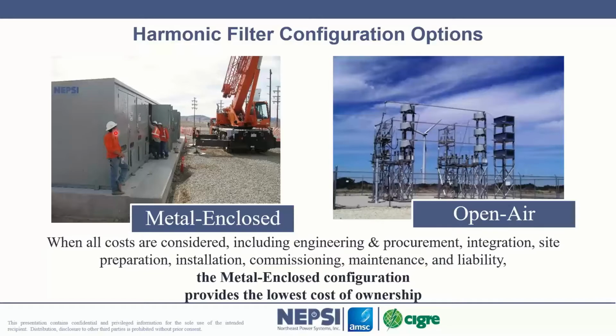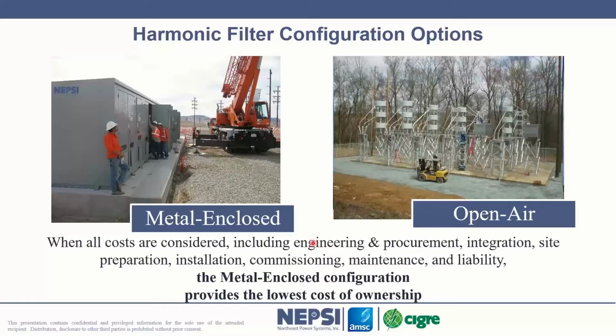The open air solution, the one to the right here, is also a filter, and it consists of air core reactors rather than iron core. So a big difference between metal enclosed and open air. The primary difference is this air core reactor. Instead of the inductor, which tunes this capacitor branch sitting behind it, being an iron core reactor, it's an air core reactor. So we're going to talk a little bit about air core and iron core reactors. And incidentally, this box here to the right, what is it? It's a resistor. So we put the resistors on top of our enclosure when we have resistors associated with our harmonic filter. In this case, you can see that the resistors are put off to the side. So open air and metal enclosed, they're the two configurations we're talking about. And we'll be touching upon both of those today.